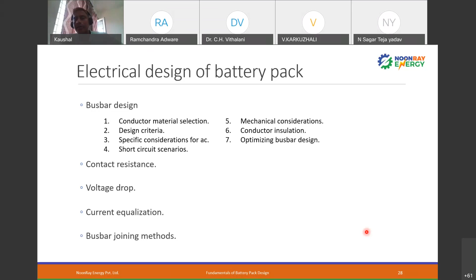So for any design criteria, for bus bar designing, what do you have to do? You have to limit the temperature. So for that, what do you do? Conductor potential drop, what is acceptable? That is the current flowing path, IR. Conductor resistance is nothing but electrical resistivity times the conductor length divided by conductor cross section. Again, resistivity is a function of temperature.